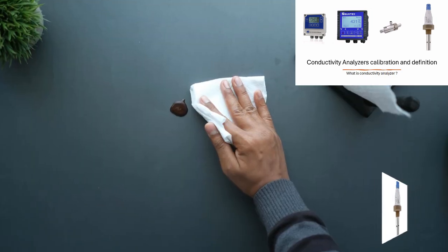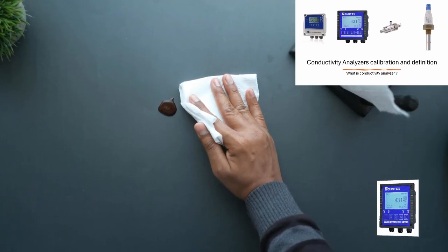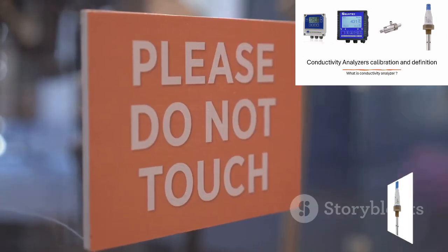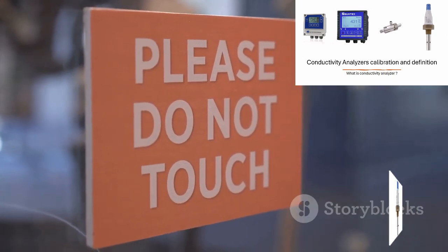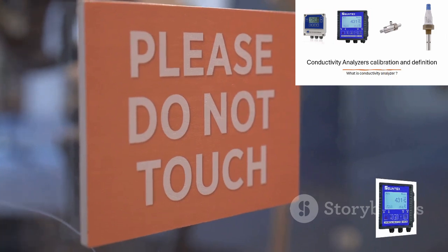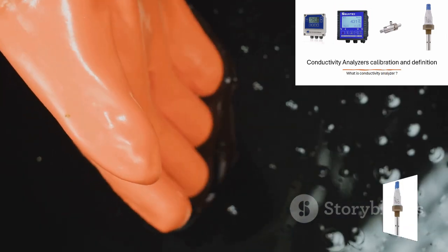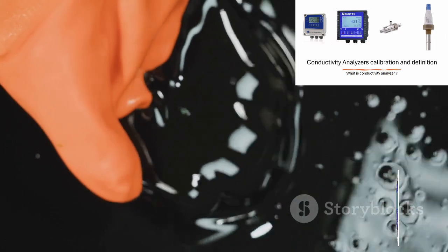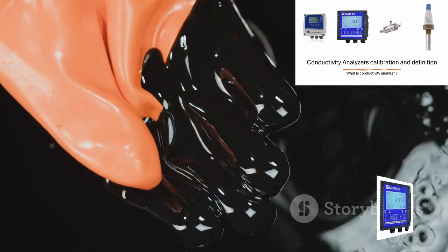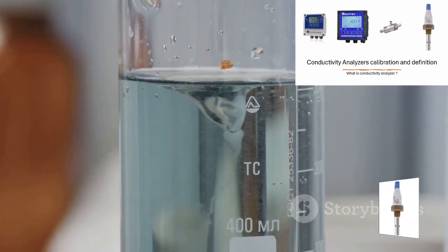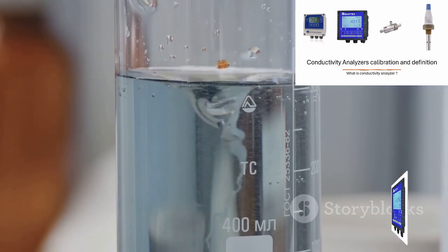After rinsing, take the sensor out and gently blot it dry with a lint-free wipe. Never, ever wipe or scrub the electrodes themselves, as this can damage their special coating. Just a gentle dab on the outside of the probe body is all you need to remove the excess water droplets before moving on.